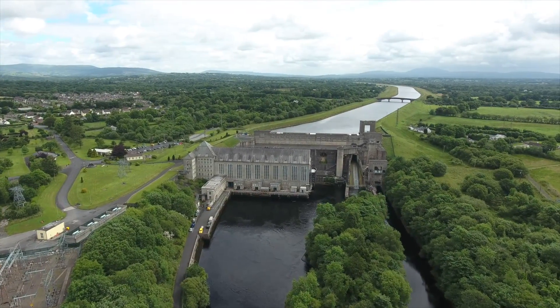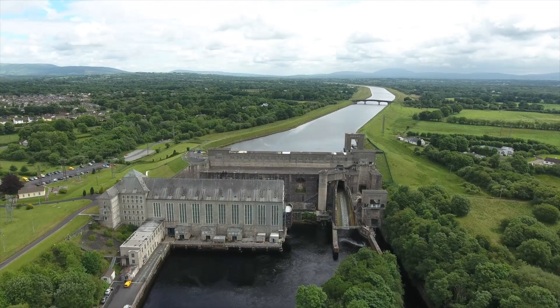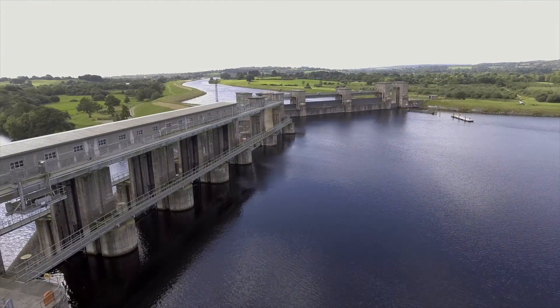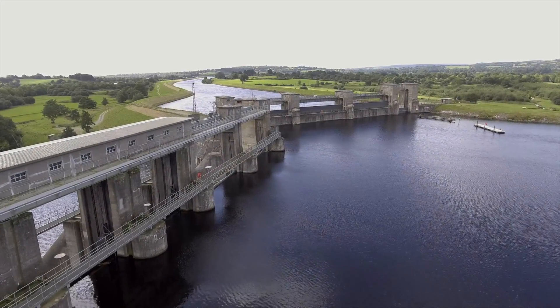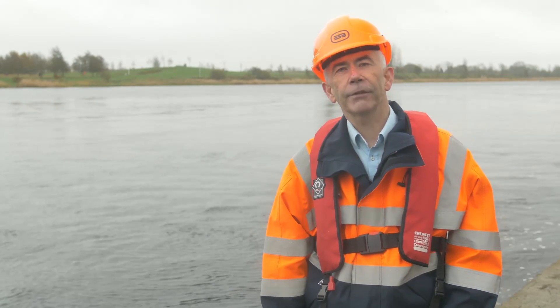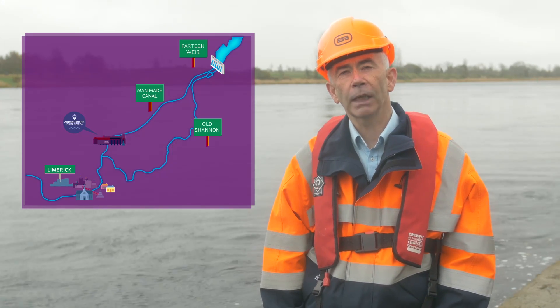ESB does not store water in Lough Allen or Lough Ree for electricity generation, and the water level in these lakes has no immediate influence on the amount of electricity produced at Ardnacrusha. We closely monitor the water level in Lough Derg, and when it rises, we increase the flow of water through Ardnacrusha, thus taking more water from the lake. Once our maximum flow capacity at Ardnacrusha is reached and if the level of the lake is still rising, we then start opening the gates at Parteen Weir. This allows the excess water to flow down the old Shannon. During large floods, the amount of water flowing in the river is greater than the capacity of Ardnacrusha, so the excess water has to be allowed to continue flowing down the old river channel by opening the gates of Parteen Weir.